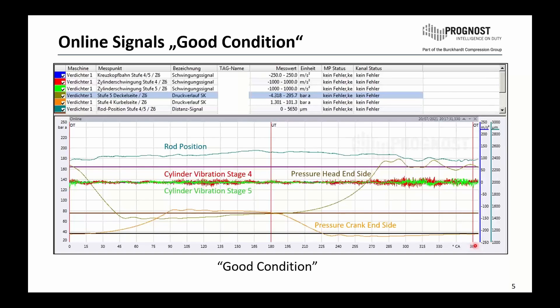One revolution of the compressor shows the compression phase on the crank end side — the fourth stage signal — including the discharge phase, re-expansion, and suction phase. On the head end side you see the re-expansion, the suction phase of the fifth stage, the compression, and finally the discharge phase on the fifth stage. This is the short introduction to the different signals. Here we have the good condition, and in the following pictures we will see how the situation gets worse.